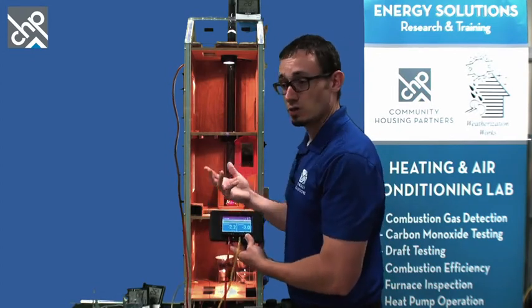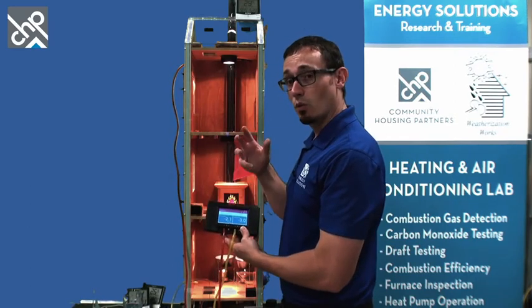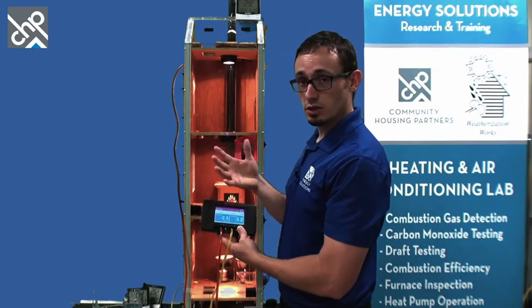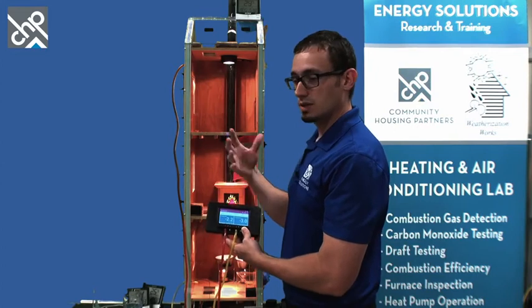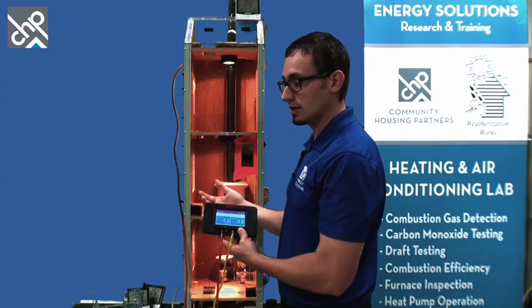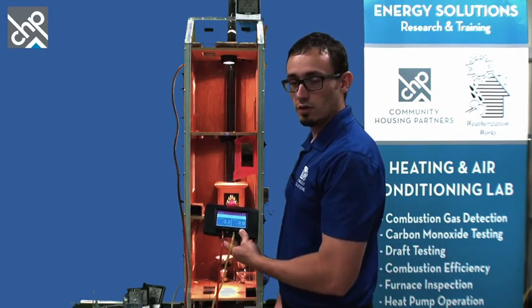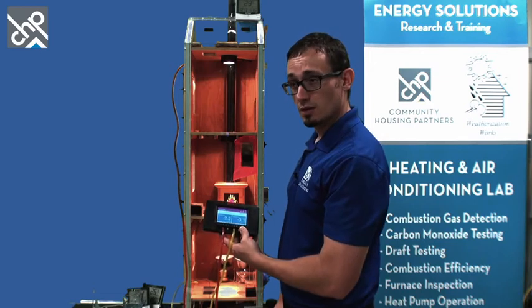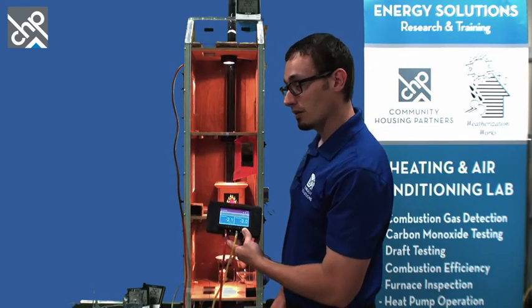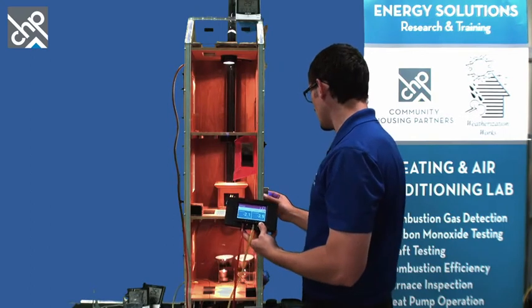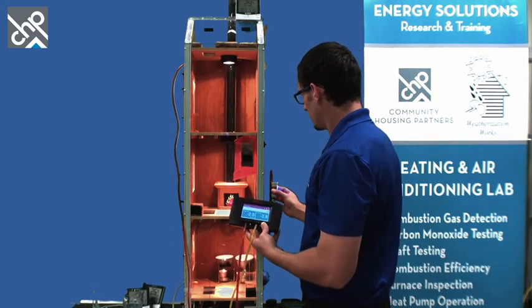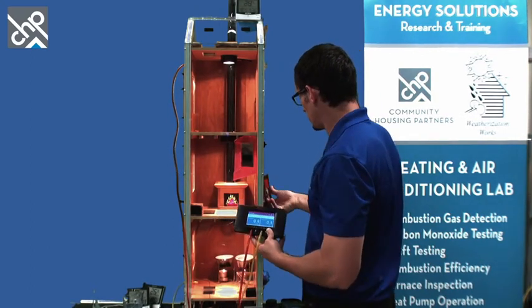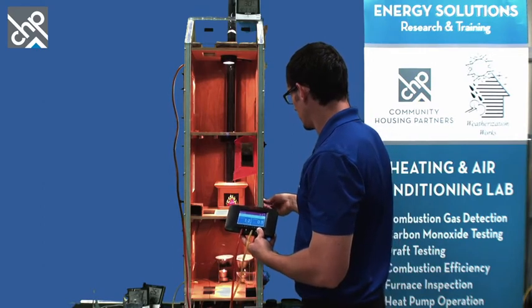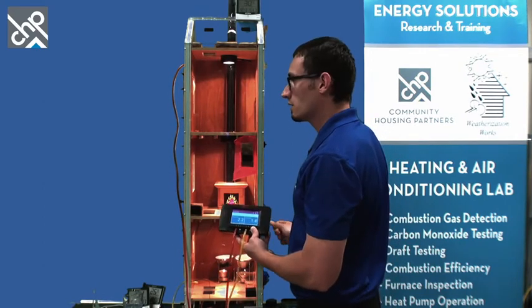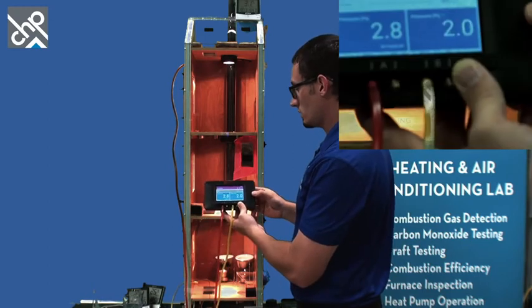You may say ASHRAE. ASHRAE doesn't specify which type of ventilation strategy is required. It simply states if you replace things or change things out, what those requirements are for those systems, but it doesn't tell you negative, positive, or balanced. So if I take my fan, turn that around, and we see what happens to the pressures.